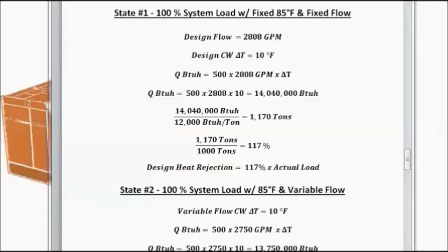So, in state 1, we can calculate the design heat rejection load from the design delta T and design flow. Right here, the heat rejection in BTUs. And we can convert this to 1,170 tons. We can compare that with the design, 1,000 tons. And we have a design heat rejection of 117% of the actual load.